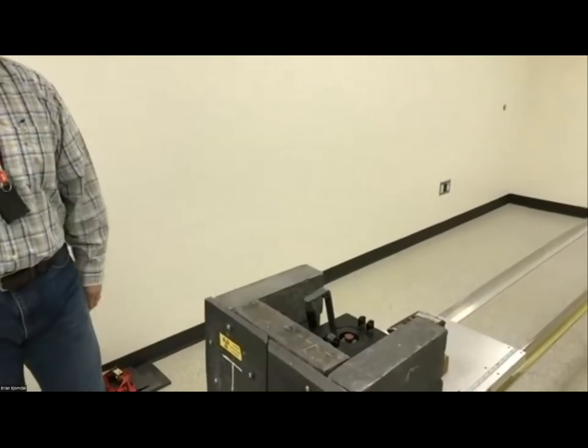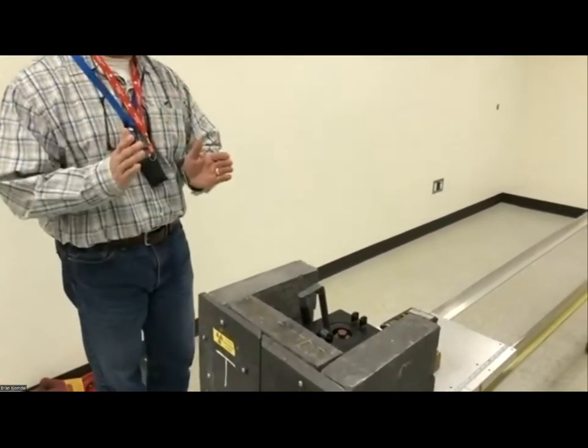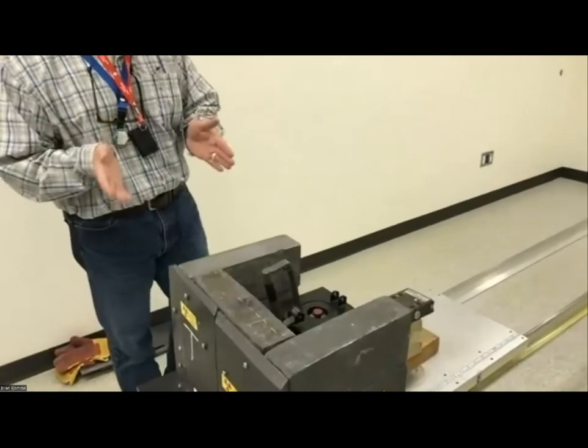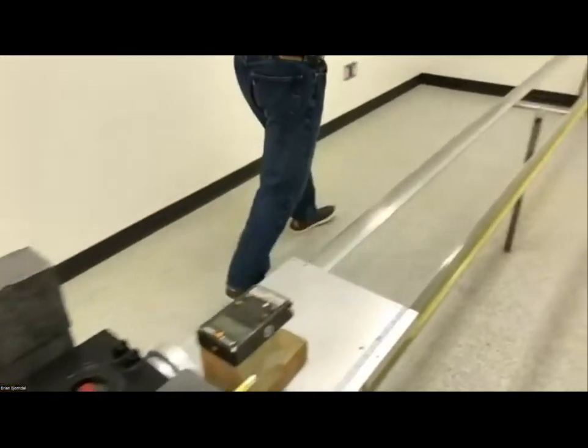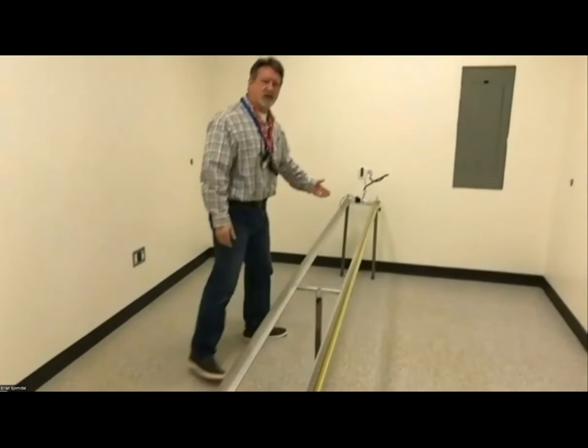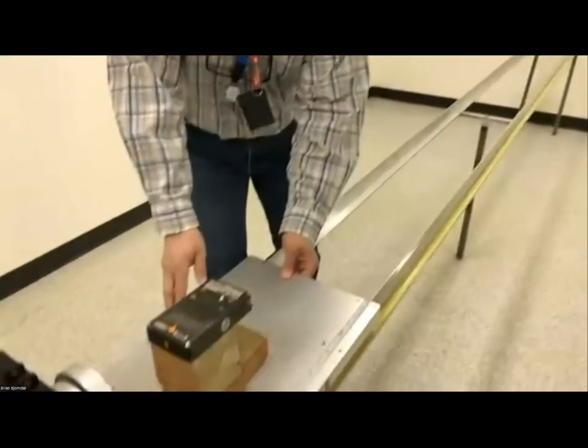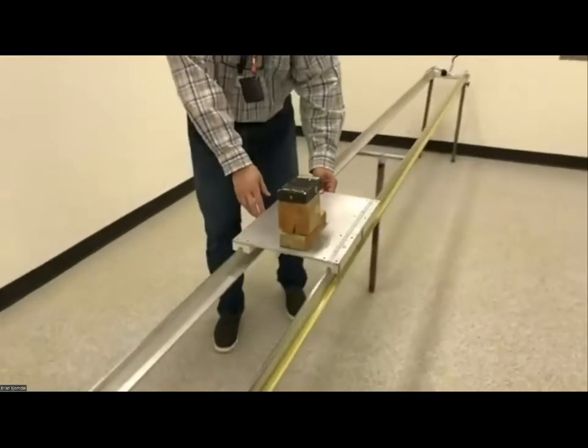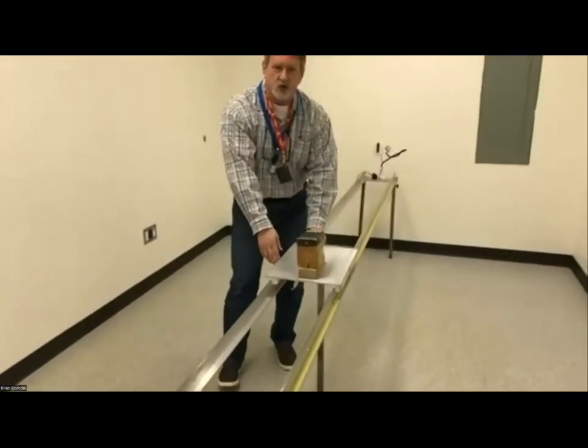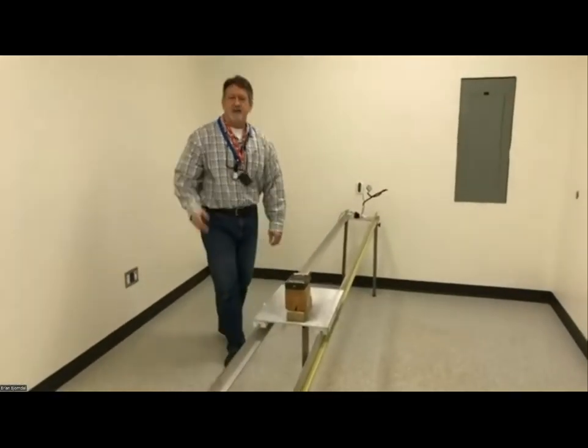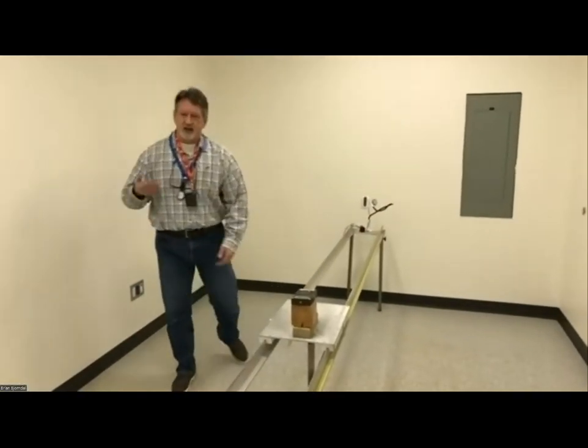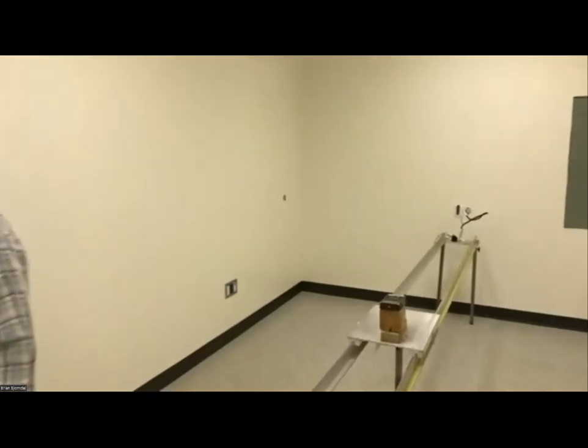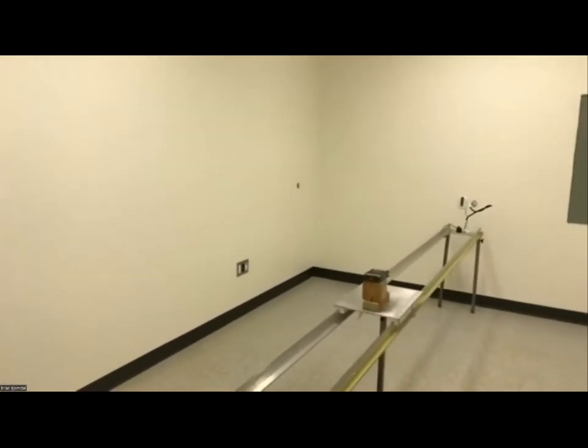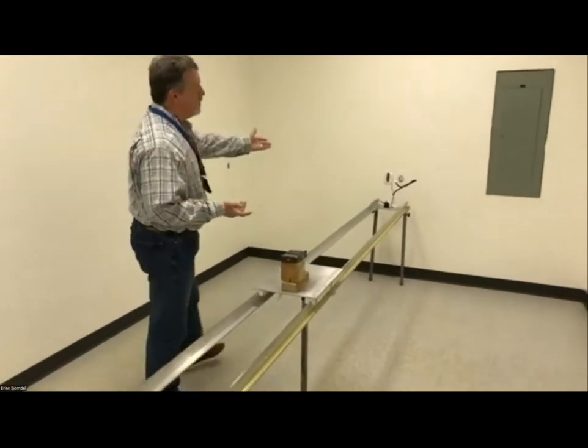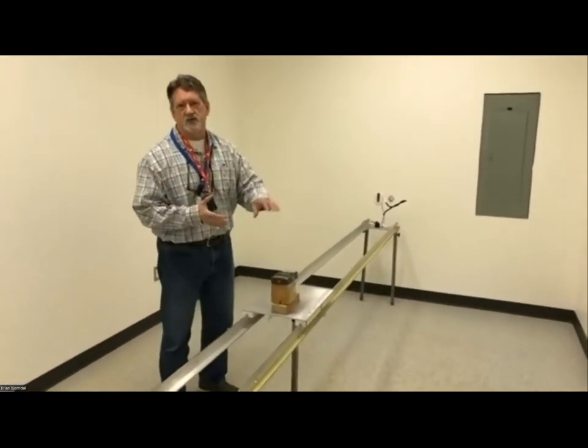So we can go from really fairly high dose rates, up to probably 50 millisieverts per hour, way down to very low doses. In the low doses, we have to move the platform way back here. So we'll move it back to a desired distance to achieve a dose rate, for example, and then we do the same process. But you can imagine, here's the practical point. If you're standing back here, you can't see this. You can't see the readout. This is when we start to implement the Wi-Fi types of cameras or CCD cameras to be able to look at it.